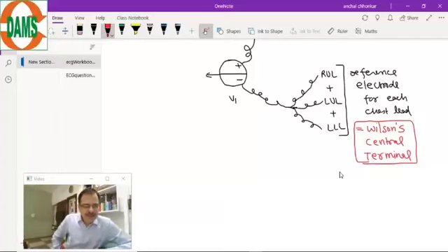This is known as the Wilson's central terminal. The net electrical difference here is zero. Here it is the zero. So this is the same for each chest lead. The meaning of true zero is that the sum combination current of these three leads is equal to zero.